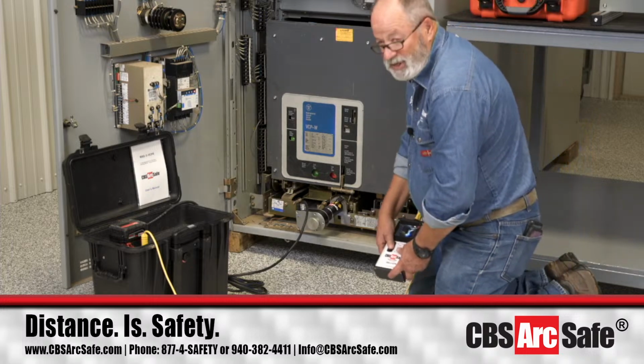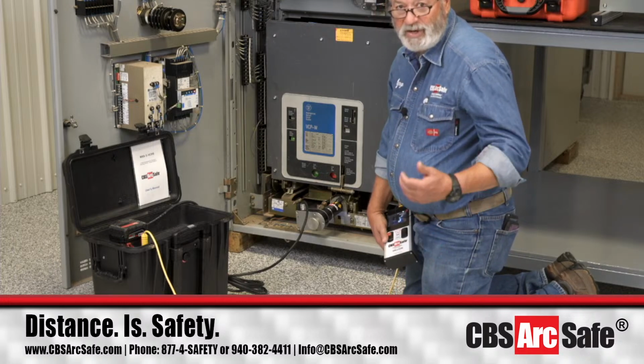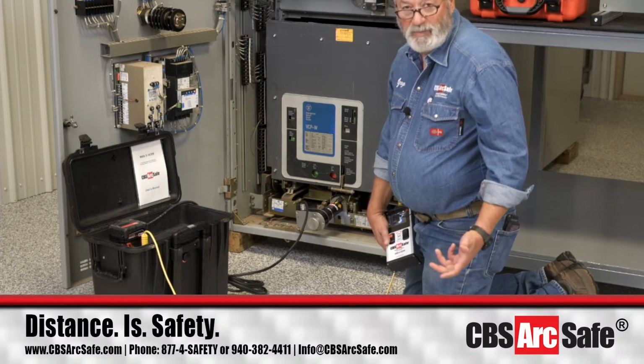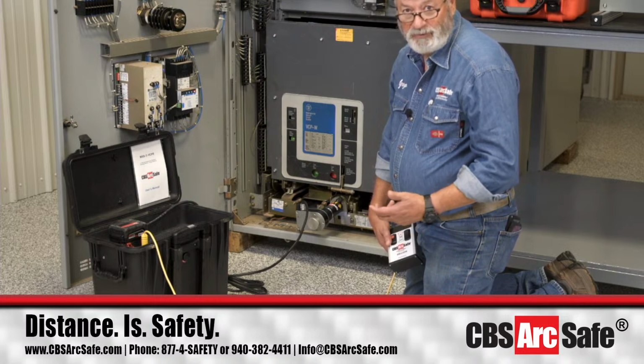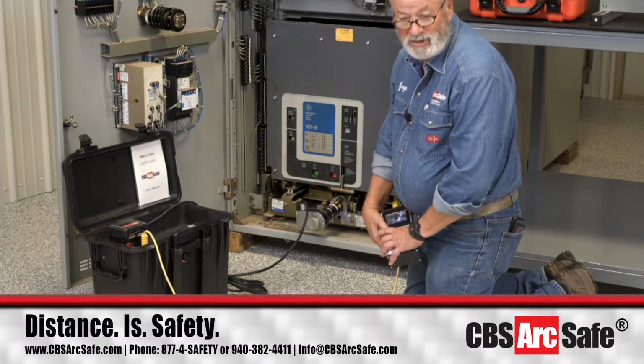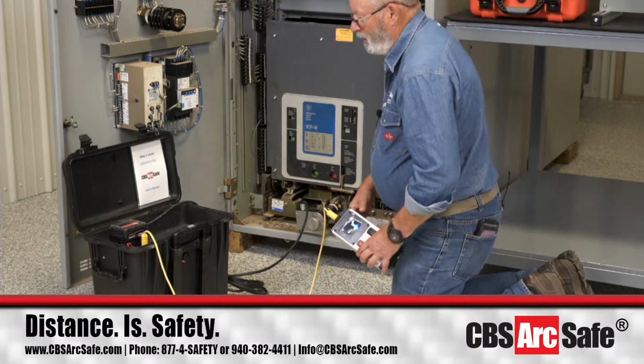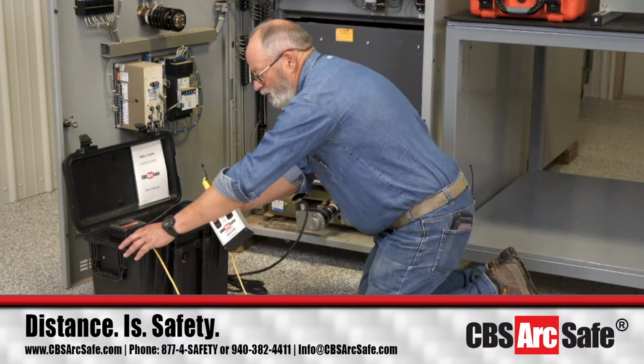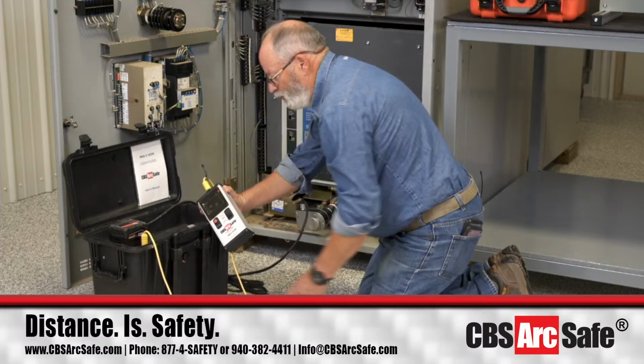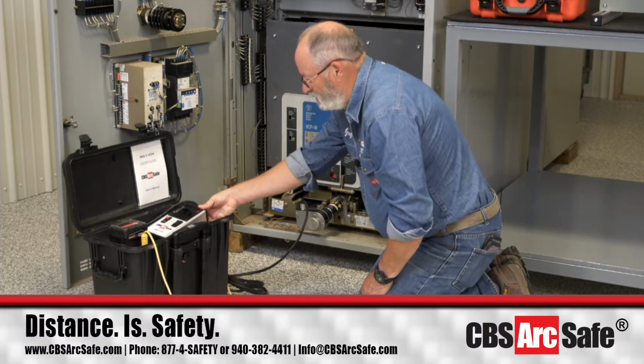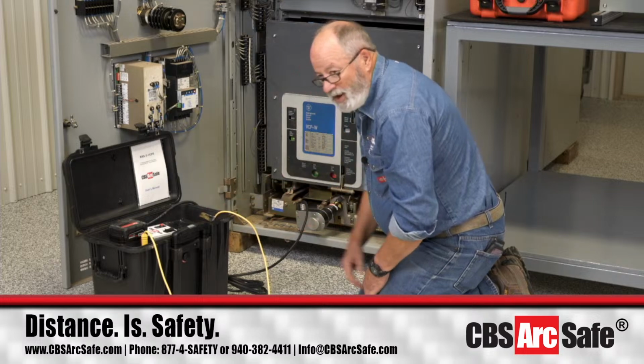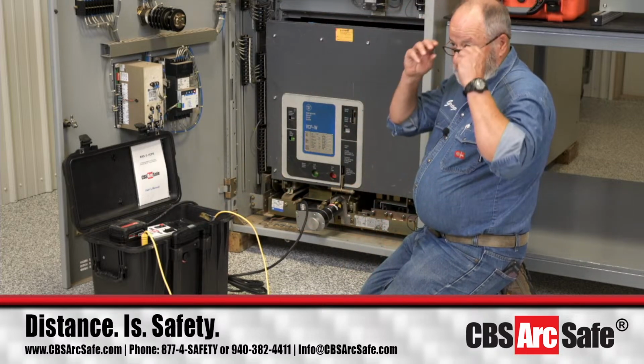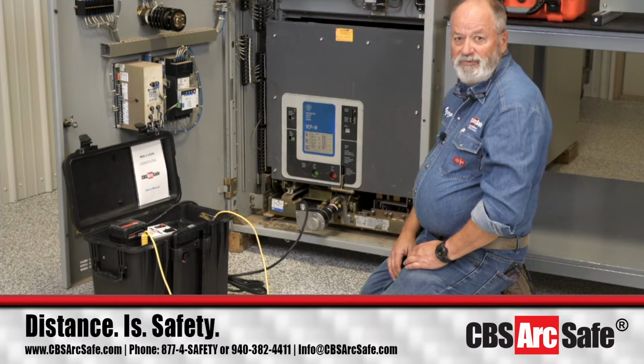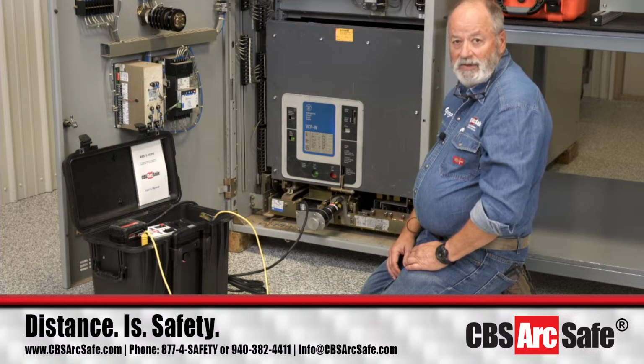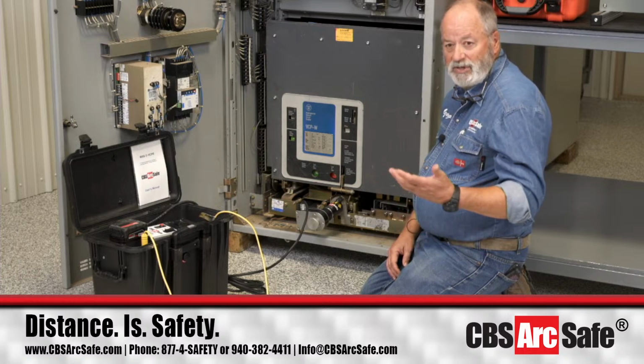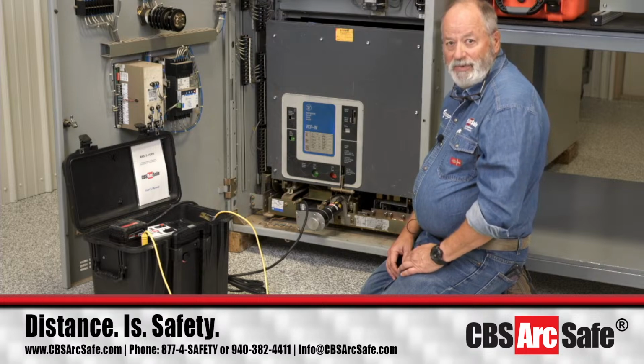So this system is capable of doing a 1200 amp up to the 3000 amp bigger breakers. It'll handle the full range of Eaton VCPW breakers. Don't be afraid to give us a call for this. We've got several different versions of things. So if you have a variety of breakers, we have over 50 different types of RSC systems we make. If there's a variation or something, we can work to adapt it to meet your specific needs.